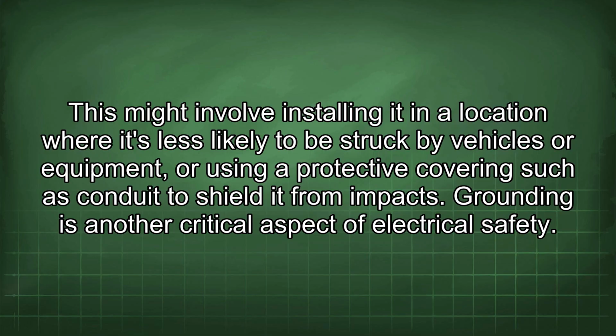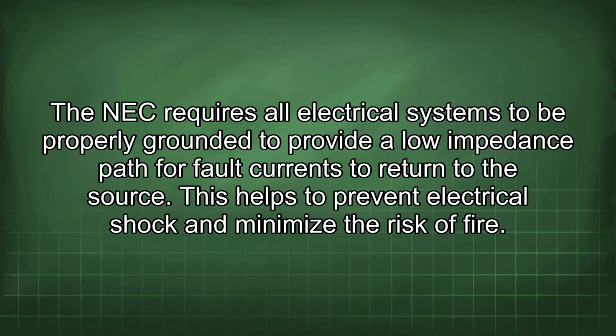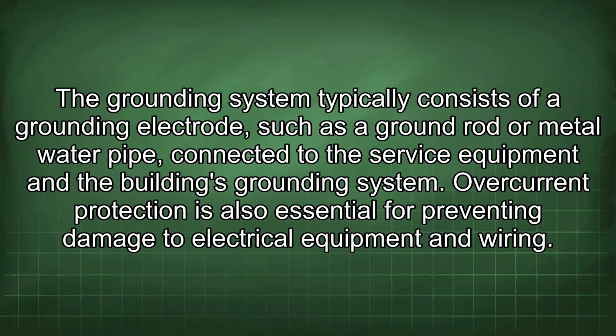Grounding is another critical aspect of electrical safety. The NEC requires all electrical systems to be properly grounded to provide a low impedance path for fault currents to return to the source. This helps to prevent electrical shock and minimize the risk of fire. The grounding system typically consists of a grounding electrode, such as a ground rod or metal water pipe, connected to the service equipment and the building's grounding system.